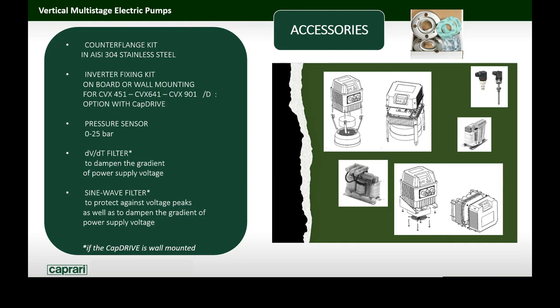As part of the CVX range extension project, Caprari are also offering a series of accessories. In particular, stainless steel counter-flange kits and inverter fixing kits on board or wall mounting. Regarding the CapDRIVE fixing kits, one of these is supplied as standard depending on the size of the motor. Specifically for electric pumps with 3-phase motors and powers of up to 15 kilowatts, there is an inverter with motor fixing kit included and an optional inverter with a wall mounting kit. Meanwhile, for electric pumps with 3-phase motors and powers of 18.5 kilowatts and over, we have an inverter with wall mounting kit included and an inverter with motor fixing kit as an optional extra.